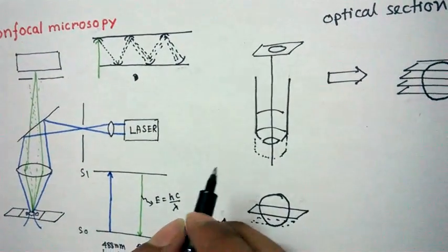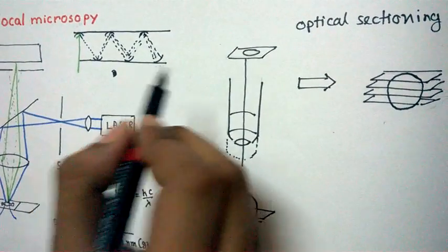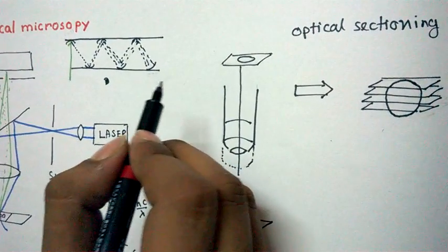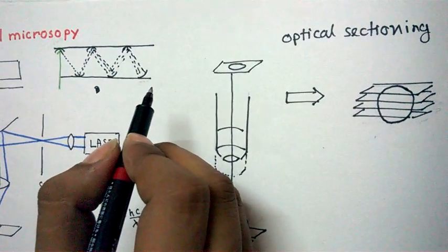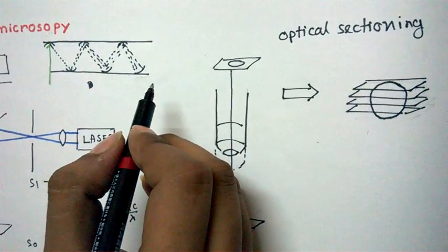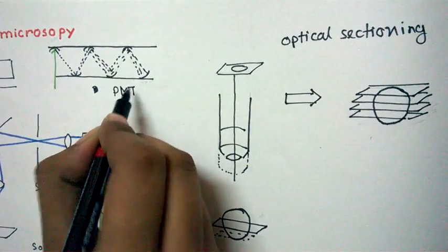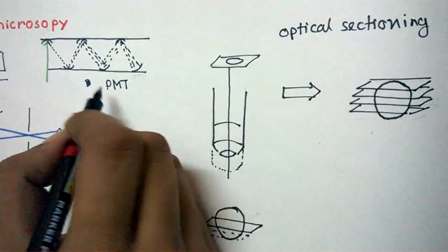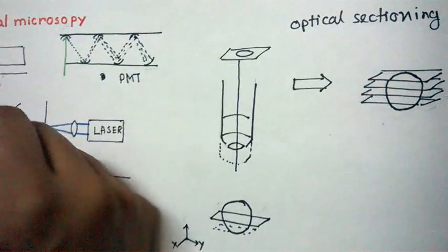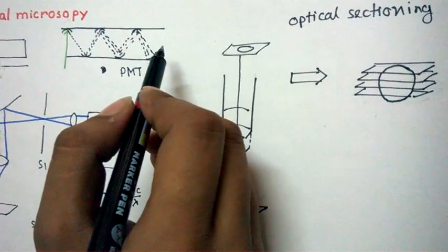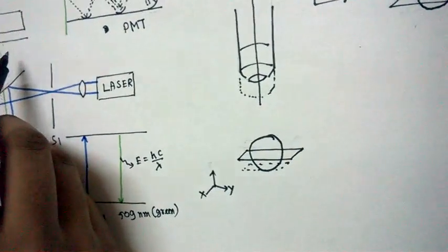That is why the name is photomultiplier tube, or PMT. Because confocal is a point scanning method, we are gathering information from each individual point, and the light coming from one point can be very small — a very little amount of light is available. Without amplifying that light we are not able to get the signal. To gain the signal, this PMT technology multiplies the light coming from the specimen and shows us an amplified signal.